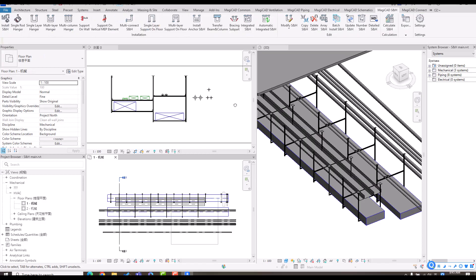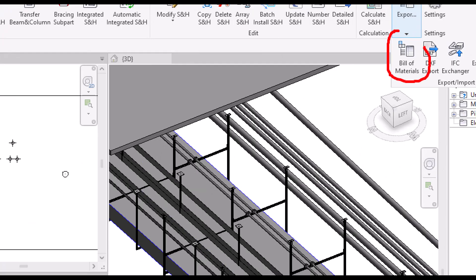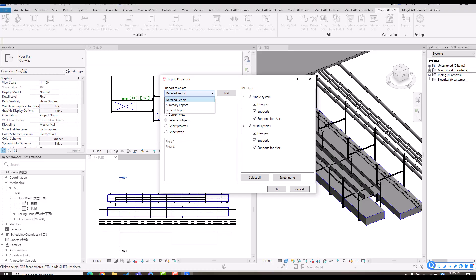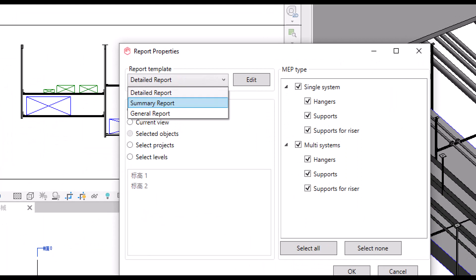For support hanger, we also have a bill of material function. We provide different LOD levels for the bill of material. We have a detailed report used for fabrication on site, showing how to cut materials and how to join them. We also have a summary report used for the purchase stage — it counts the total number of subparts across all instances in the project or floor.